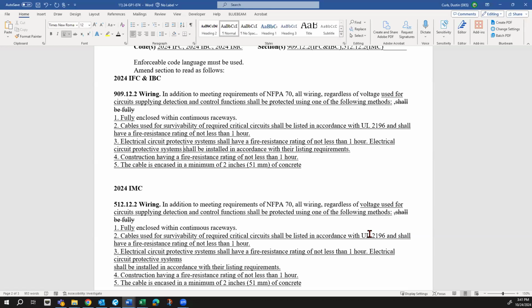Something that says, we want to see protection, survivability of these circuits and systems—not just for the fire alarm side, but also like this. For a fire pump, you're required to have 1 hour; a fire pump is a critical system, so that protection is required to be 1 hour. It should be standard when you're talking about detectors not part of a smoke control system, or not required because of the smoke control system. This gives them a tool to do it.